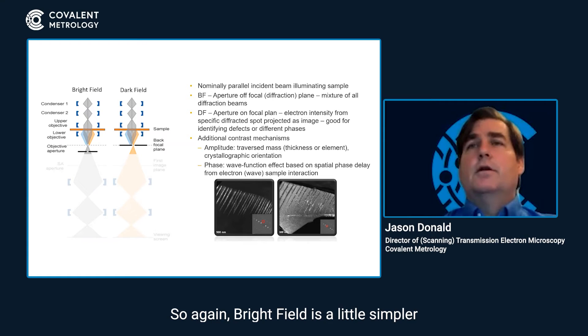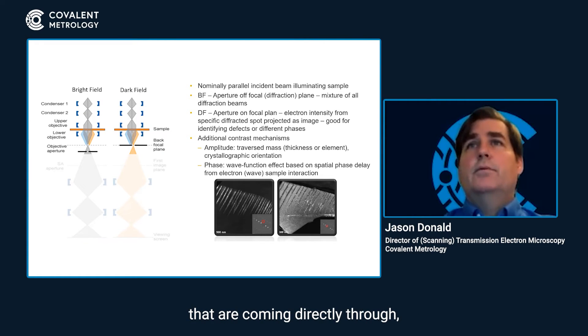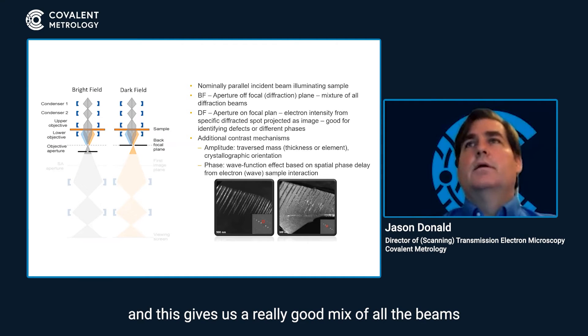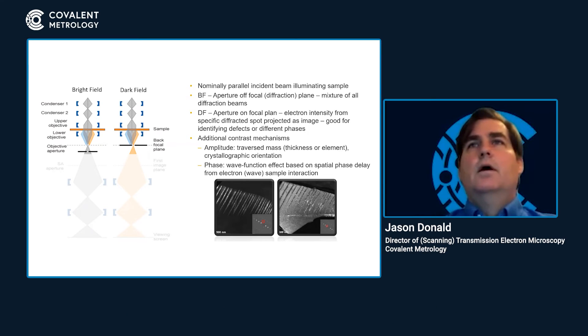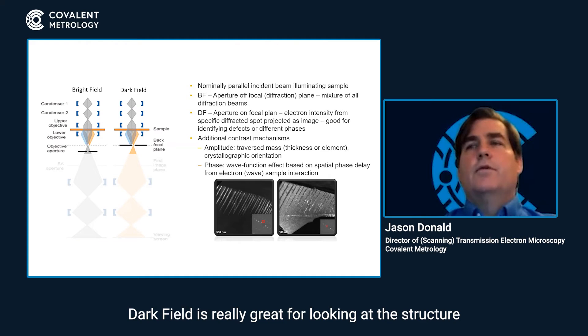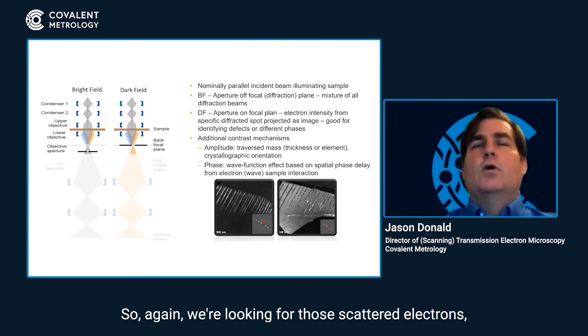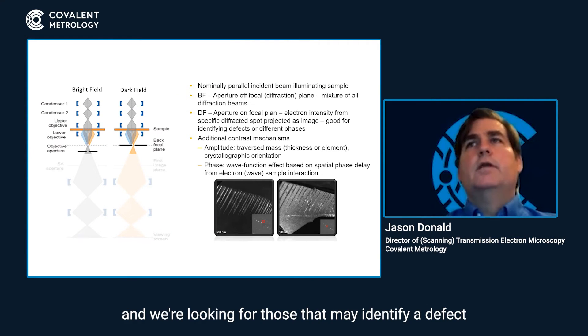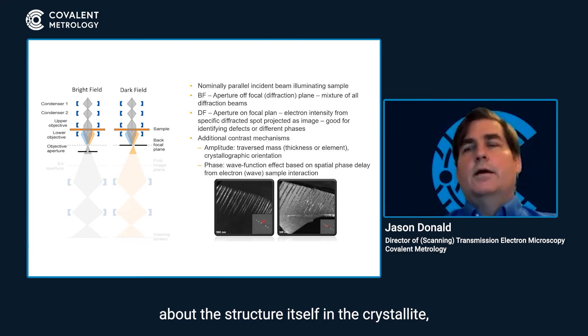Bright field is a little simpler — we're only looking at those electrons that are coming directly through. This gives us a really good mix of all the beams and allows us to have high contrast and good data. Dark field is really great for looking at the structure and looking for things that may be disassociated. We're looking for those scattered electrons that may identify a defect or a crystalline structure. We get great information about whether the structure itself is crystalline or not, or the diffraction.